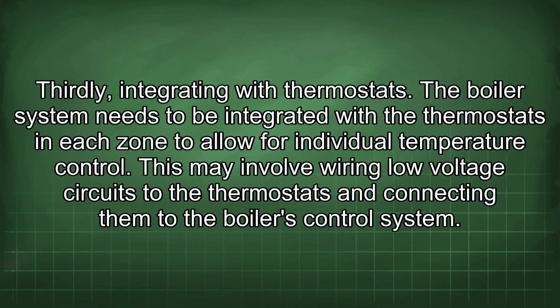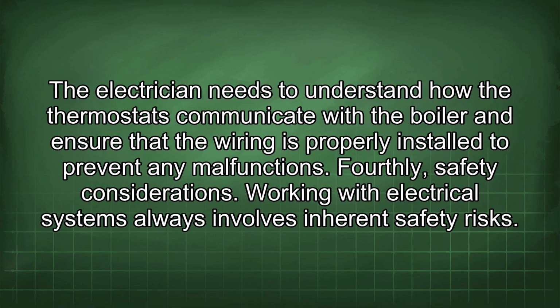Thirdly, integrating with thermostats. The boiler system needs to be integrated with the thermostats in each zone to allow for individual temperature control. This may involve wiring low voltage circuits to the thermostats and connecting them to the boiler's control system. The electrician needs to understand how the thermostats communicate with the boiler and ensure that the wiring is properly installed to prevent any malfunctions.